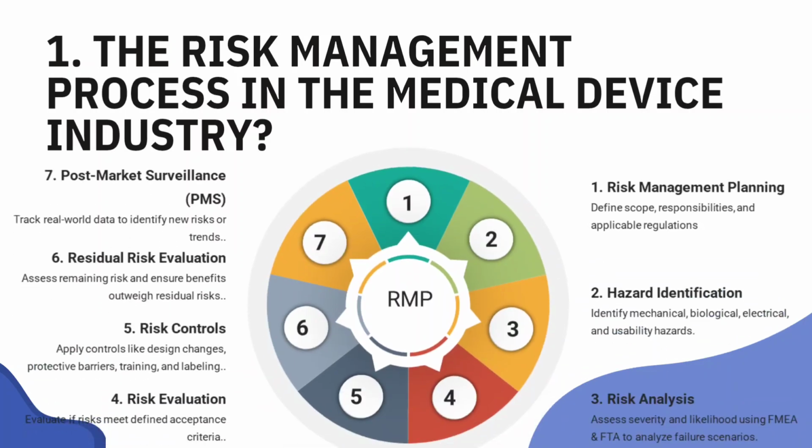I would like to start the interview by asking a simple and basic question. 1. Can you walk me through the risk management process in the medical device industry? First, we start with risk management planning. What's the scope? Who's responsible? What regulations apply? Then we move to hazard identification, where we systematically pinpoint potential hazards. Could be mechanical, biological, electrical, usability related, anything that could pose a risk.